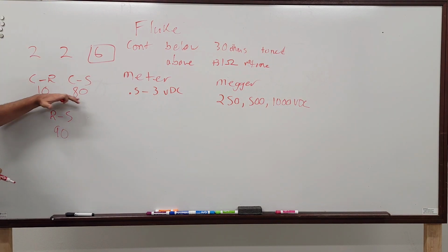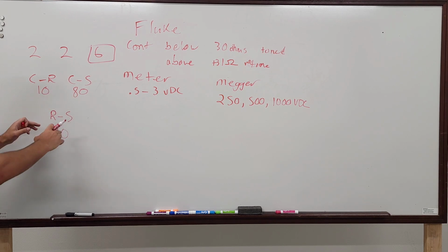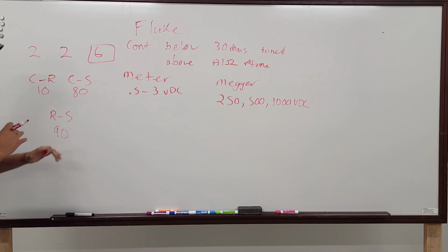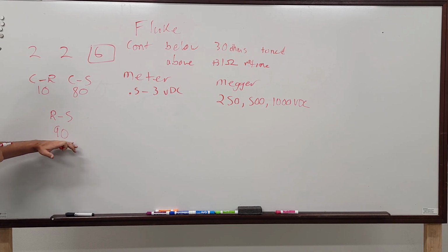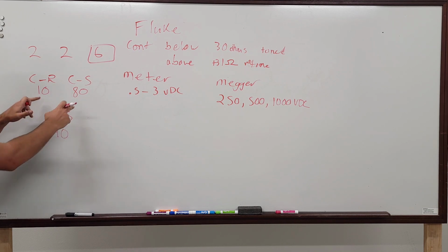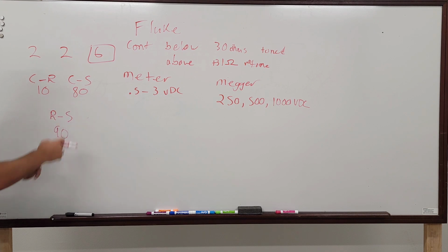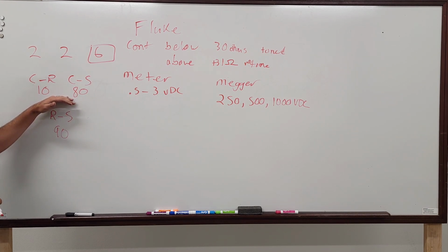This is a direct correlation to these, because literally this is reading through these. It's these two combined to get to this. Right. So if this is considerably different than the math you did in your head on this, something is wrong. Now the values change per the motor. These aren't hard set values. But the math is the same.